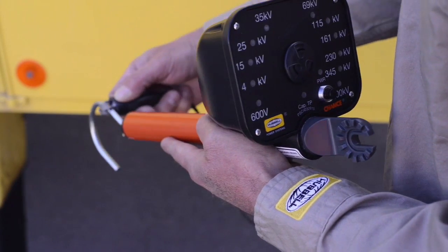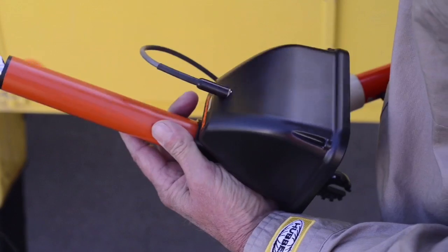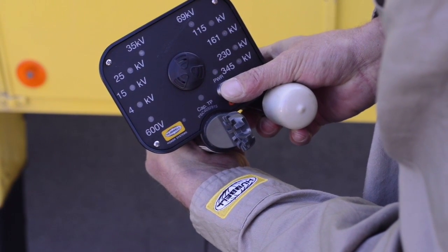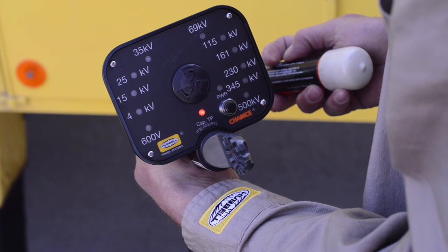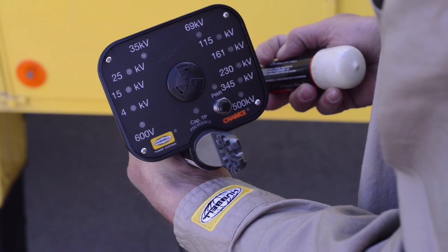First, connect the alligator clip onto the HV hooks. Then, insert the probe into the back of the HV housing. This pre-check must be performed before each use. Press and hold the power button for two seconds. This will initiate an internal self-test. Notice how the HV sequences through a series of all display ranges, verifying it is in operable condition. After the self-test, the power LED continues to flash, indicating the HV is ready for use.